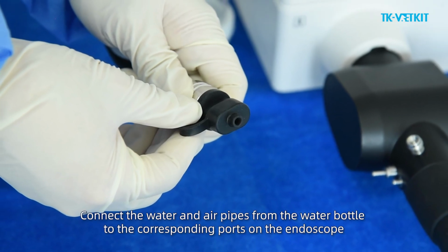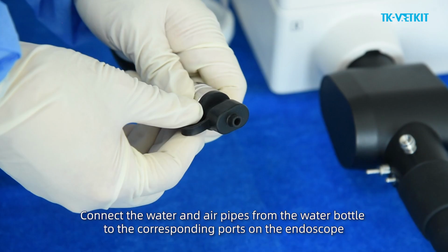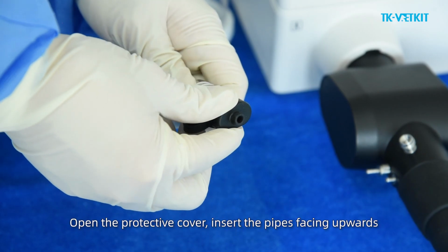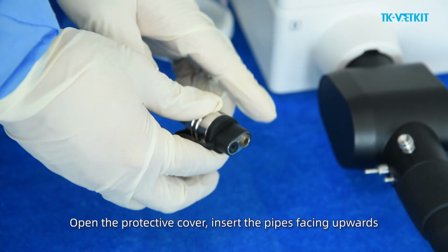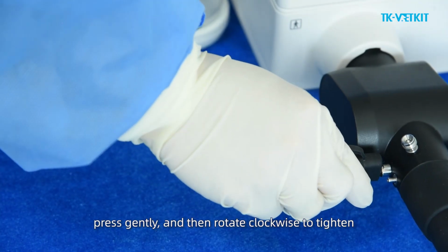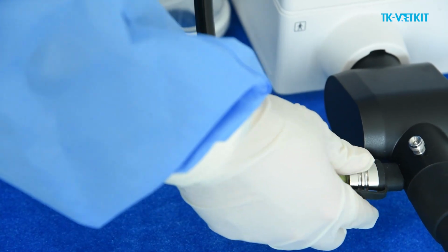Connection of water bottle with the endoscope. Connect the water and air pipes from the water bottle to the corresponding ports on the endoscope. Open the protective cover. Insert the pipes facing upwards. Press gently, and then rotate clockwise to tighten.